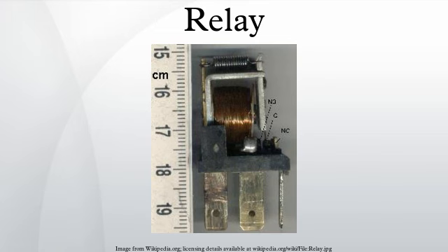The thermal and magnetic overload detections are typically used together in a motor protection relay. Electronic overload protection relays measure motor current and can estimate motor winding temperature using a thermal model of the motor system that can be set to provide more accurate motor protection. Some motor protection relays include temperature detector inputs for direct measurement from a thermocouple or resistance thermometer sensor embedded in the winding.